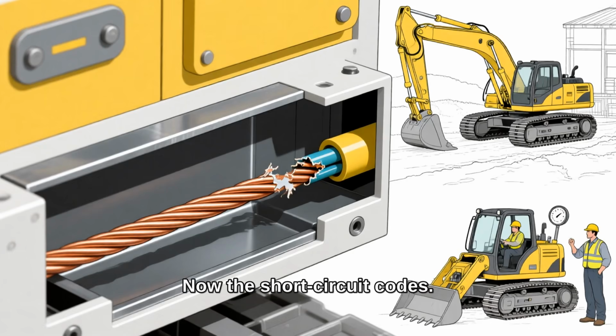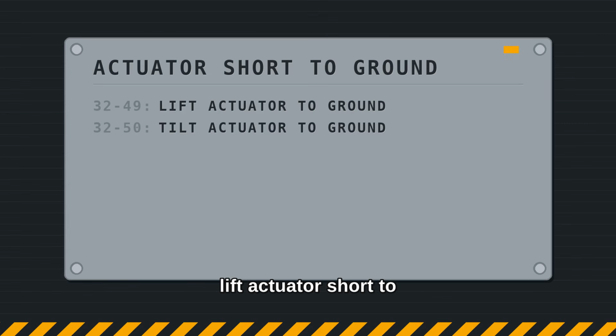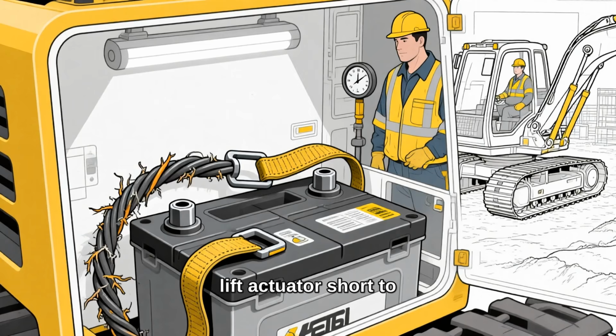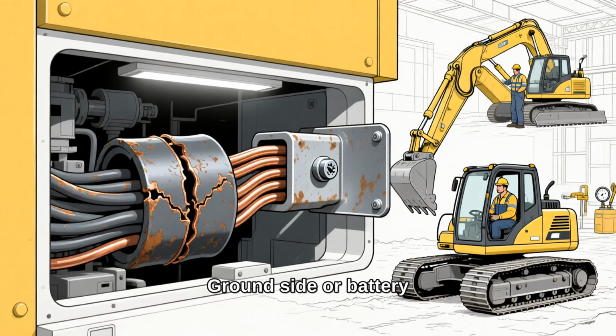Stick around. Now the short-circuit codes. These are the most specific things this panel will ever hand you. 3249 is lift actuator short to ground. 3250 is tilt actuator short to ground. 3251 is lift actuator short to battery. 3252 is tilt actuator short to battery. Ground side or battery side. That's a wire rubbing bare on steel versus a wire touching power it shouldn't.